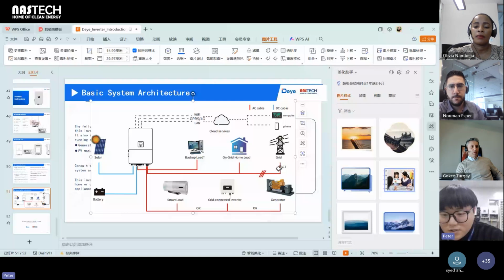And next, for example, if the on-grid inverter is 200 kilowatt. Yeah, there's the second part. We need to use hybrid in the night. If the on-grid inverter is 200 kilowatt, and hybrid also should have some PV panel for itself, we need to know how much power can generally be produced in the daytime. So if it's 200 kilo, I think your hybrid inverter should also be similar to 200 kilo.